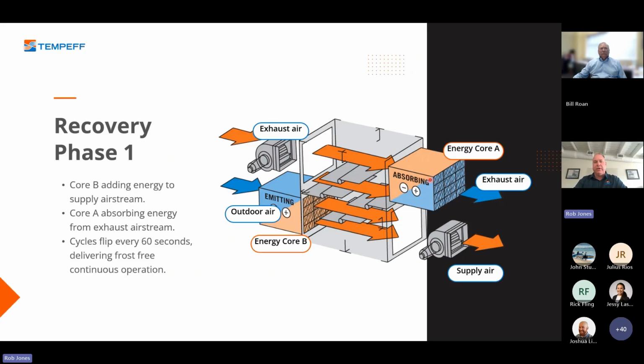The exhaust air is moved over to energy core A, which is actively scrubbing out and retaining that energy. It's charging, and then it's exhausted to the outside atmosphere. Over here, the cold outdoor air is coming through energy core B that is already charged. The air is being warmed over to the supply air and into the building. It will do this for exactly 60 seconds, and 60 seconds is the key here.